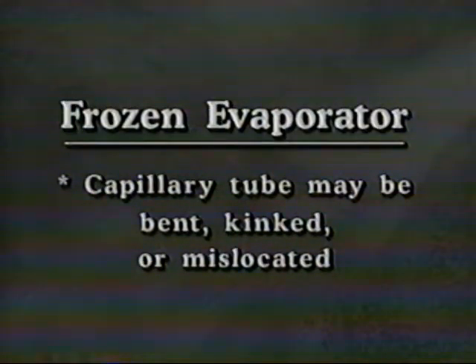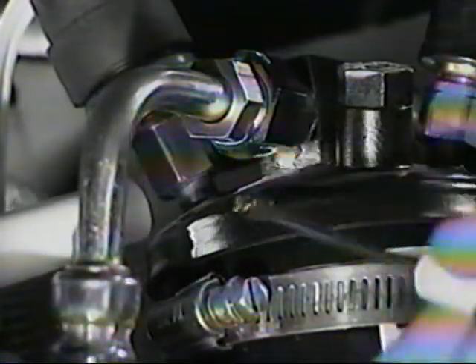The line from the receiver dryer to the evaporator should feel warm. An icy spot could indicate a restriction. Finally, the line from the evaporator to the compressor should feel cold. A warm line could indicate a bad expansion valve. An icy line indicates that the expansion valve could be stuck open or that the system has been overcharged with R12. If the evaporator freezes over, a thermostatic switch capillary tube may be bent, kinked, or mislocated, conditions which can also lead to other symptoms of other AC problems. Any oily spots on the lines or at the fittings could mean a system leak.